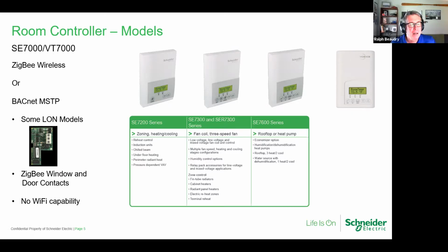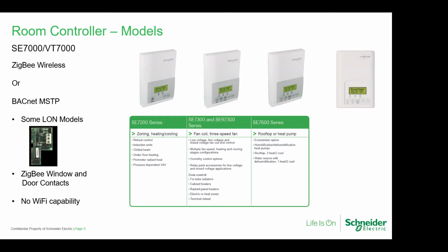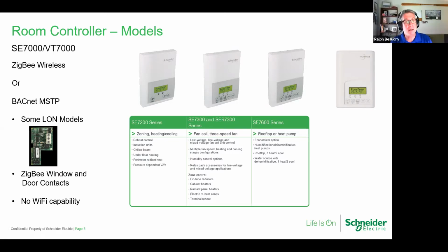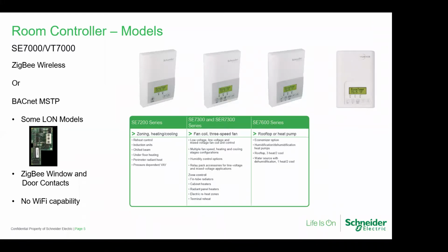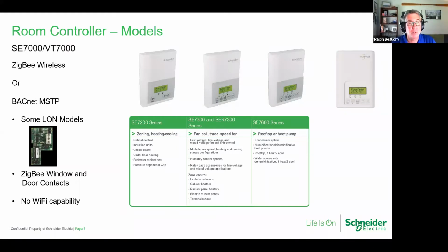Okay, cool. So I can add to the 7000 series a ZigBee wireless card - it talks ZigBee wireless to a gateway. I can add BACnet MSTP, so it's an 'or', right? I can have ZigBee, or I can have BACnet MSTP, or I can have LON on a limited amount of models. There's no Wi-Fi capability in the 7000 series.